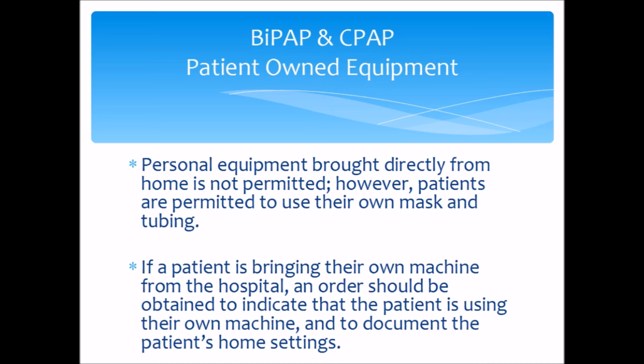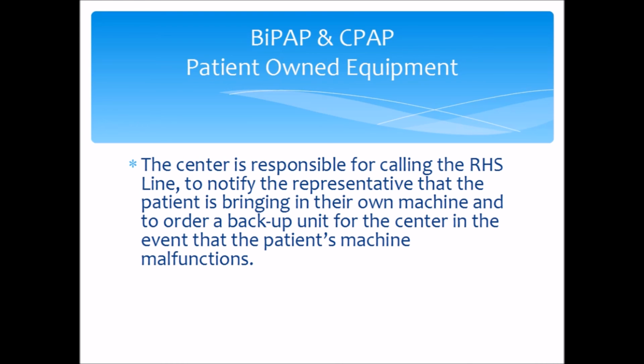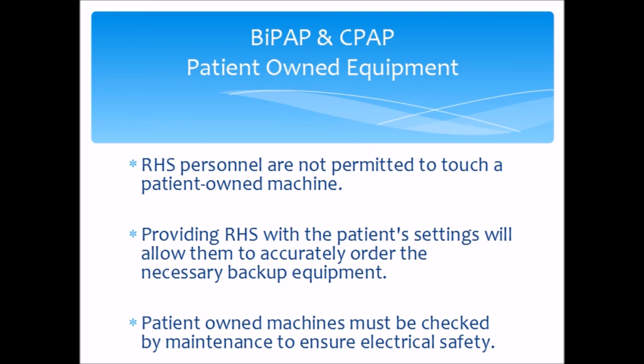If a patient is bringing their own machine from the hospital, an order should be obtained to indicate that the patient is using their own machine and to document the patient's home settings. The center is responsible for calling the RHS line to notify the representative that the patient is bringing in their own machine and to order a backup unit for the center in the event that the patient's machine malfunctions. RHS personnel are not permitted to touch a patient-owned machine. Providing RHS with the patient's settings will allow them to accurately order the necessary backup equipment. Patient-owned machines must be checked by maintenance to ensure electrical safety.